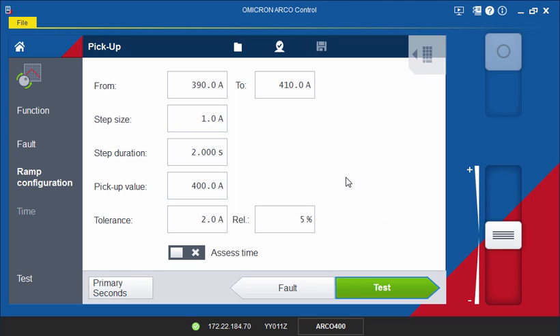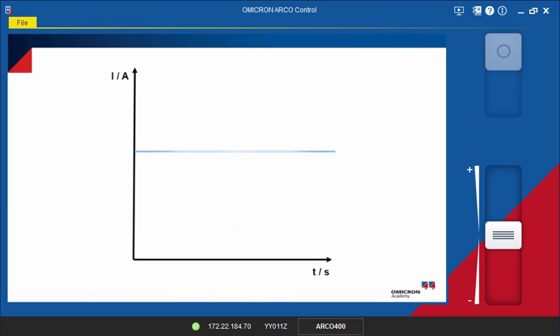To make the procedure easy to understand, we will support our explanation with diagrams which include all the parameters required to perform the test. The controller's pickup value has been set to 400 amps.